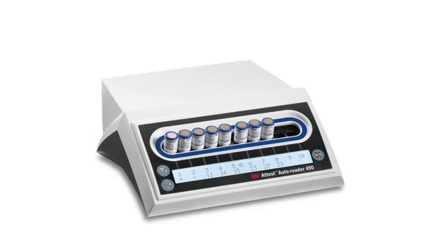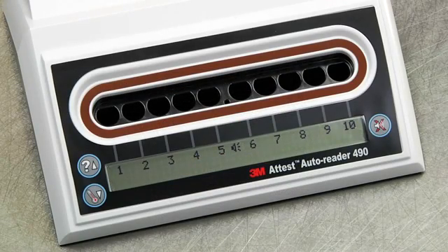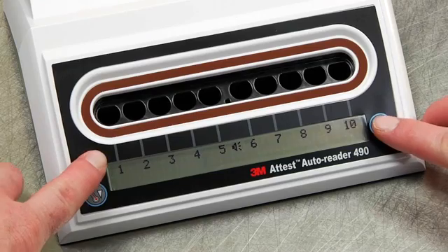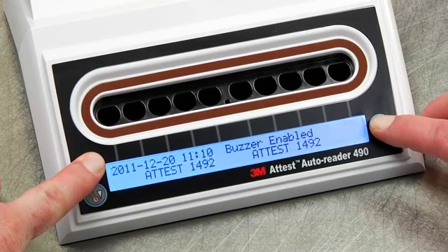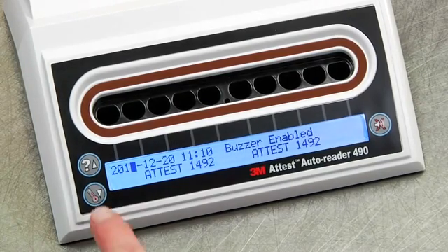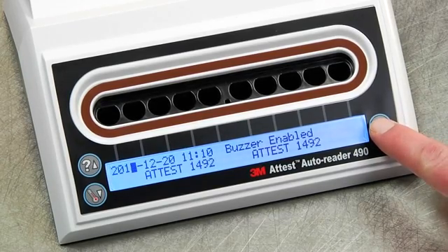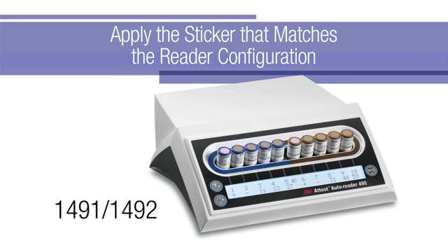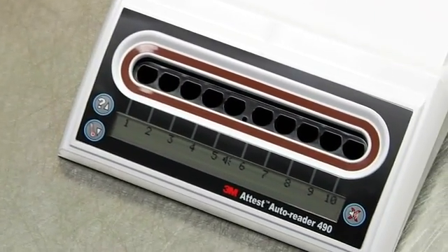To save counter space, Auto Readers can be stacked two units high. Before configuring the wells, make sure the Auto Reader 490 is empty. Press the Info and Alarm Off buttons on the front of the unit simultaneously and hold for three seconds to enter the configuration mode. Next, use the Up and Down buttons to program the clock, buzzer, and incubation well configuration you want. The Alarm Off button acts as an Enter key and moves the flashing cursor to the next changeable setting. Be sure to apply the color-coded sticker that matches the Auto Reader configuration that you need. Your Attest Auto Reader 490 is now ready to use.